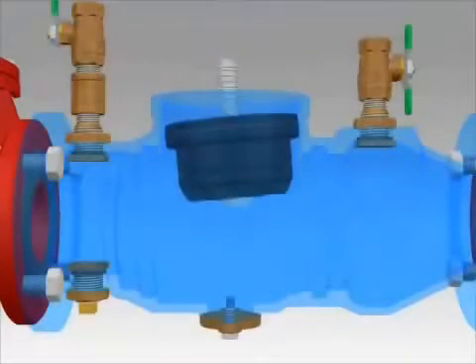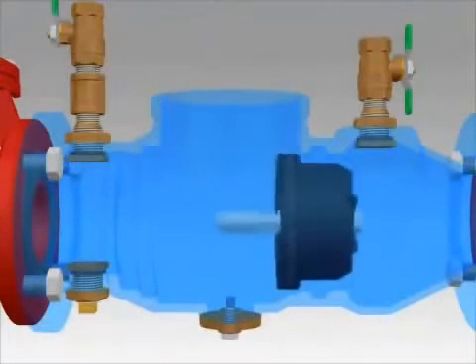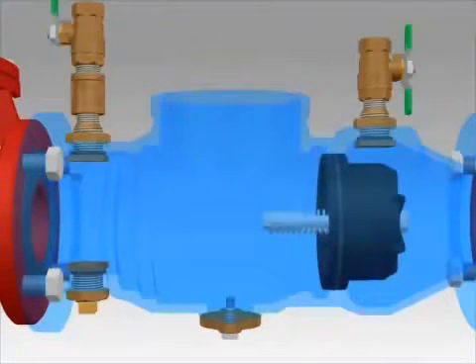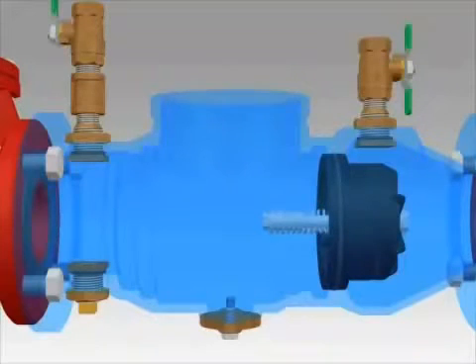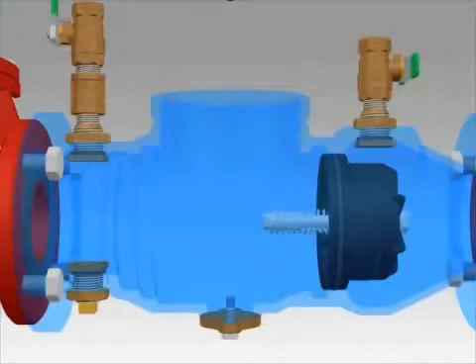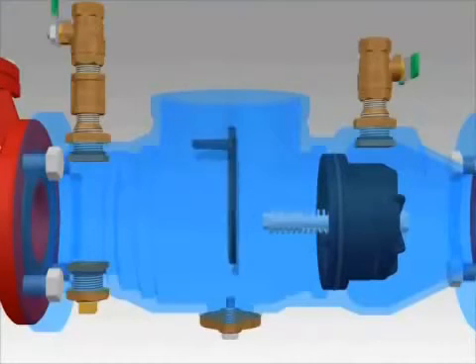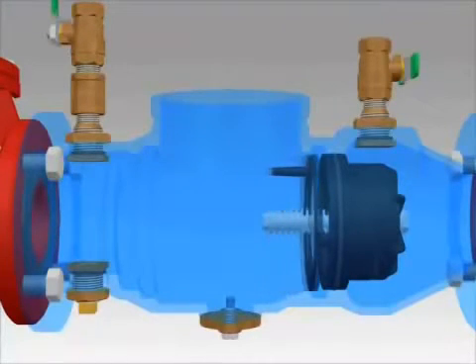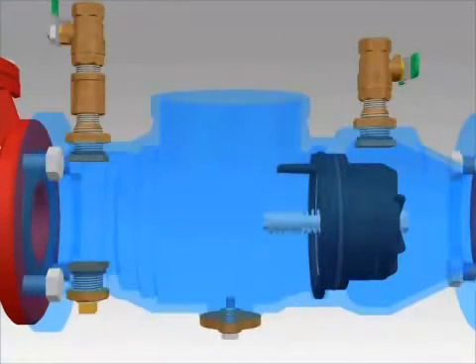After servicing the number 2 check, install it in the body making sure it is completely seated. The groove for the seat retainer should be completely exposed. If valve was not drained, water may squirt from the number 4 test cock as the check is installed. Close the number 4 test cock to hold the check in place. Install the plastic retainer by inserting one end into the body groove and then sliding your hand around the face of the retainer, pushing it into the groove as you go.